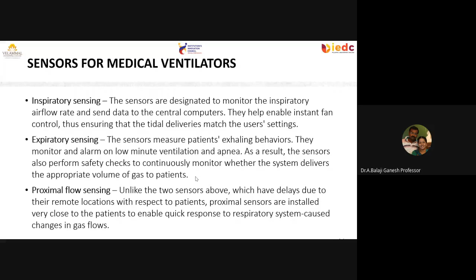And for ventilators also, a number of sensors are being used or required: inspiratory sensing, expiratory sensing, proximal flow sensing, because the oxygen flow is very important. The flow sensor detects breathing in and breathing out, the CO2 and the O2, and it is very important in any kind of ventilator in the market. So these are the sensors being used: the inspiratory sensor senses the airflow rate and sends the data to the central computer, whereas the expiratory sensing would detect the exhaling behavior. Of course, you need to take care of this.